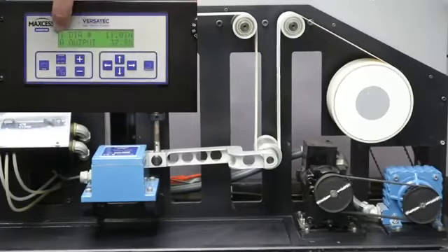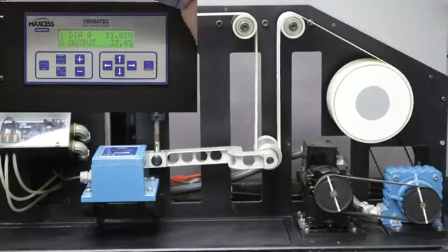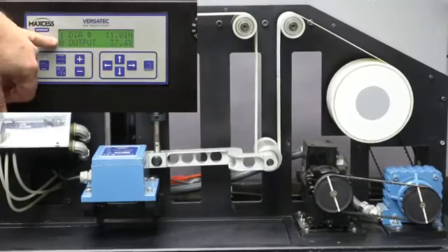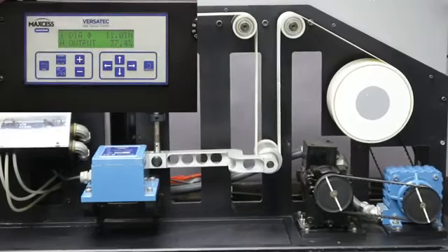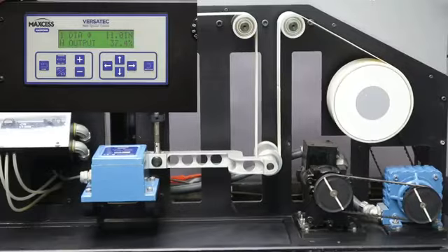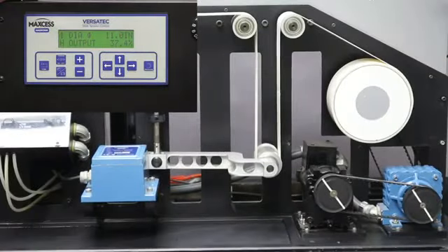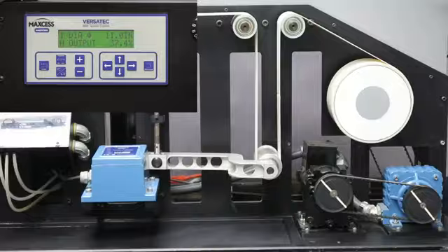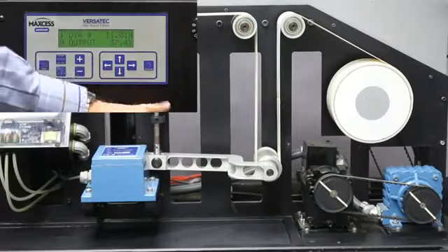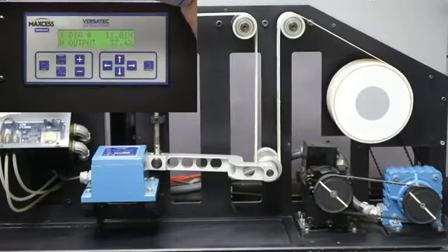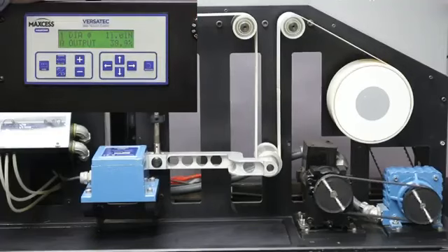In this case, we've got a switch here. And if you look at the screen, you can see it says A, which is automatic. When I hit that stop, it goes through a stop sequence and goes into hold. And what that did was it turned the integrator off, which pauses or holds the control loop. So now that I've used the controlled stop, when I turn it back on, I start right back off from that point.